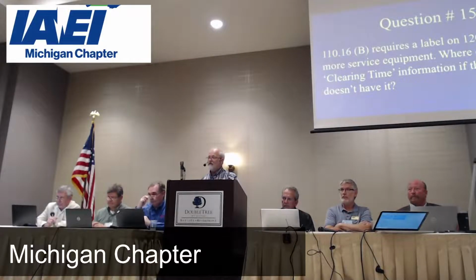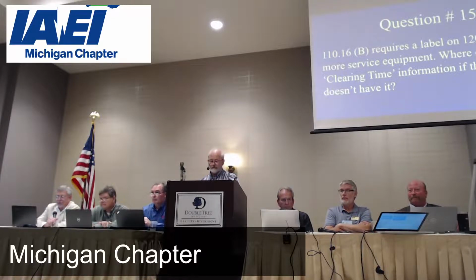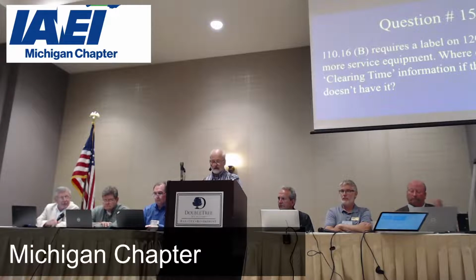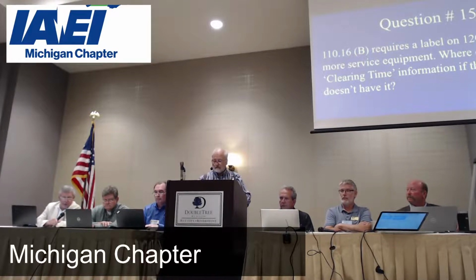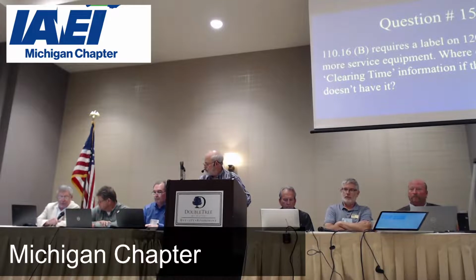Thanks for the clarification, because that's an important piece. I just think what he's saying is sometimes it's hard to get that from the utility. Yeah. I know they're struggling with it, but they're well aware of the requirement. You can get the information online. Can you? Yeah, most utilities that I've ever dealt with will have published tables on all of the transformers that they use. And it's based on the impedance and the voltage and the size of the transformer. And if you know those three parameters, put in a plug for Eaton, FC squared. All you need to know is wire size, length, transformer size, transformer impedance, and voltage, and it will give you available fault current, even if the utility is not cooperative.